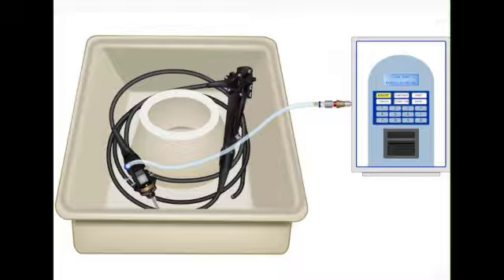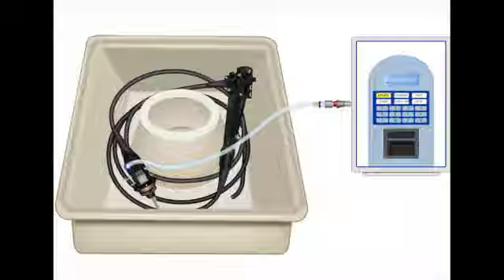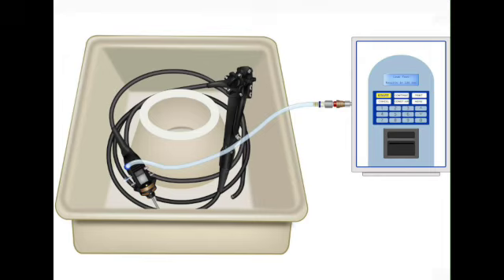Okay, let's start with what seems to be the gold standard, the one you see most often in busy endoscopy centers, the dry mechanical leak test. All right, this is the one that uses an automated machine. So what's the prep for that? It's not just plug and play, is it? Not at all. The prep is so important. First, you have to remove all the detachable parts. So like the suction valve, the air water valve? Yep, the biopsy cap too. All of them. They get processed on their own. Then you connect the special leak testing valve from the scope to the machine.